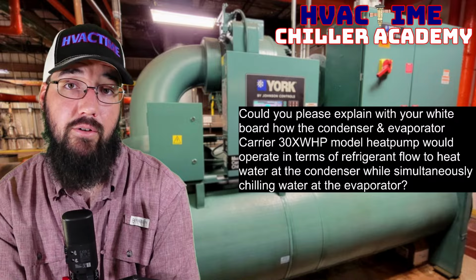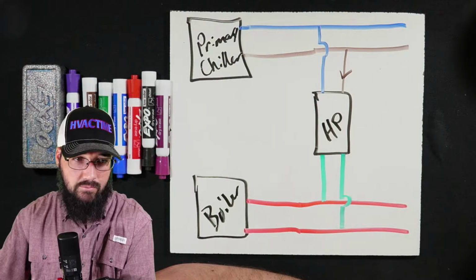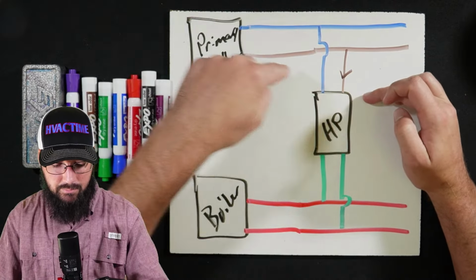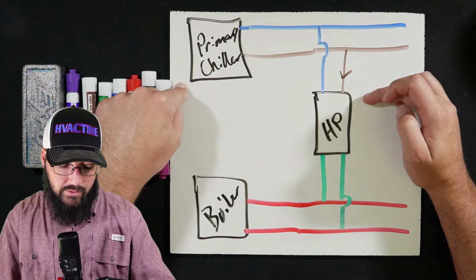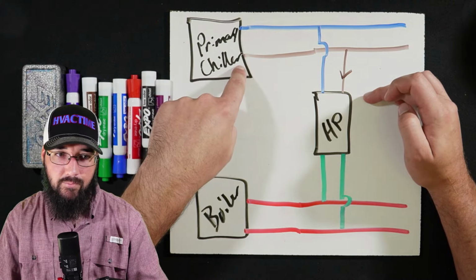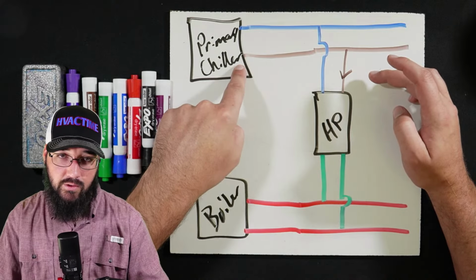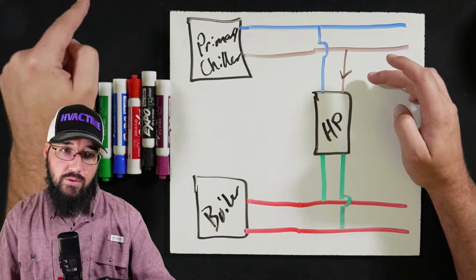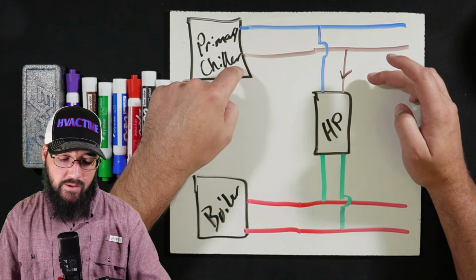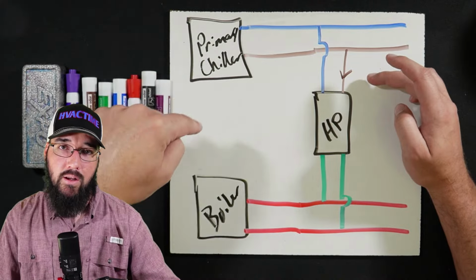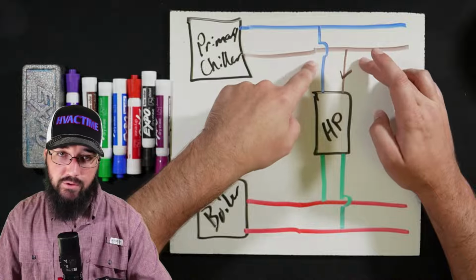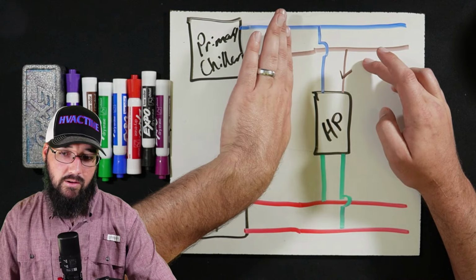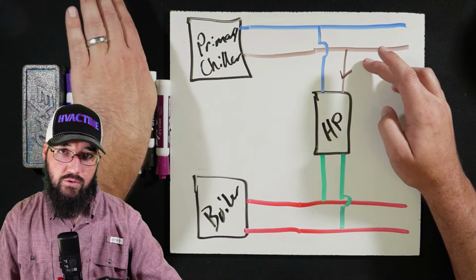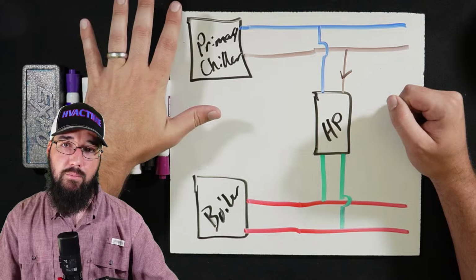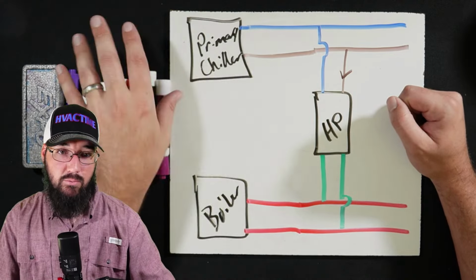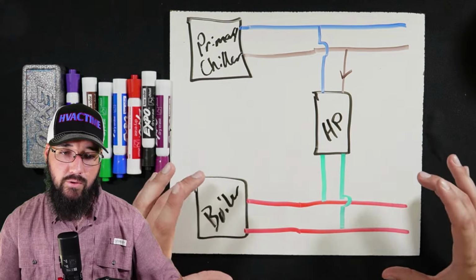So in order to achieve better efficiency, we can come back to this here. If we were piped in over here, while we remove load from the tower, we're not helping this chiller at all. Whereas if we can pull some load off of this chiller, then we, by default, also pull load off of the cooling tower, because now we're not having to move as much heat into the condenser water, hence the cooling tower has to work less. So by pulling it off of the chill water loop, the cause and effect would be this entire side of the system gets to unload a bit, because it has less heat being pushed to it, and it's being rerouted for the hot water circuit.